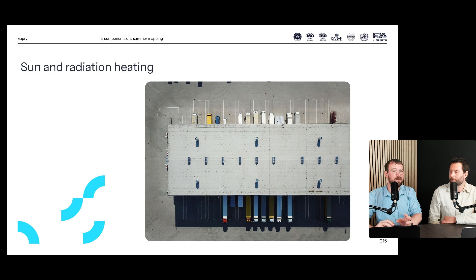For power failure studies, for example, if there is a surrounding external influence where it's hotter during the summertime, most likely that power failure study is going to show larger deviations, or quicker deviations, of temperature over time. And the same goes for door opening studies.